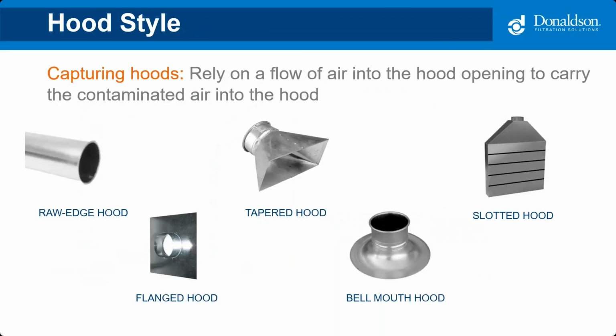In my experience with battery recycling, the dust collection system is sometimes connected to a machine or a series of machines with built-in hoods or a simple dust port connection that only require an airflow or static pressure for our design. That's usually provided by the machine manufacturer. When a hood is required, the most common hood style is a capturing hood, which relies on establishing a general airflow pattern into the hood opening to produce a capture velocity at a specified distance from that hood. There are 5 main types of capturing hoods. You can see them on the screen. The most common that we see are the slotted hoods and the tapered hoods.